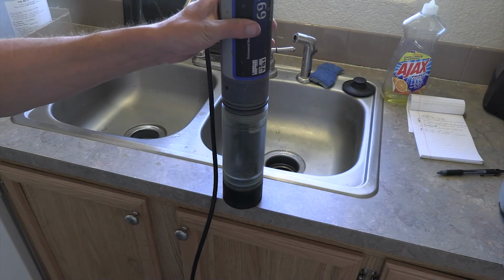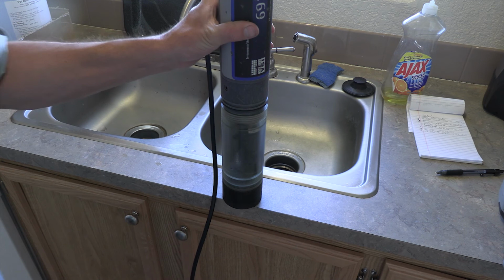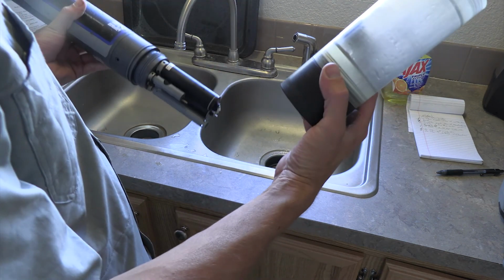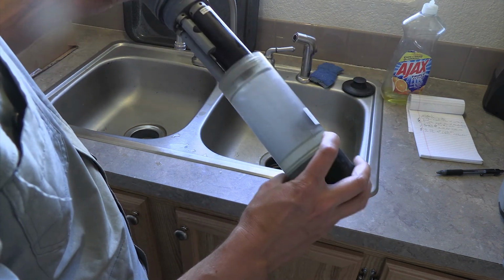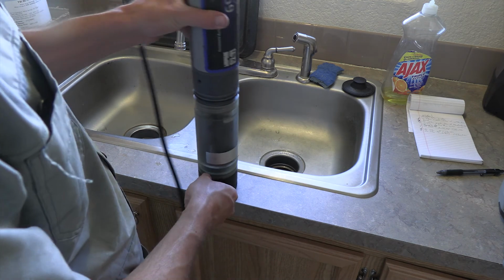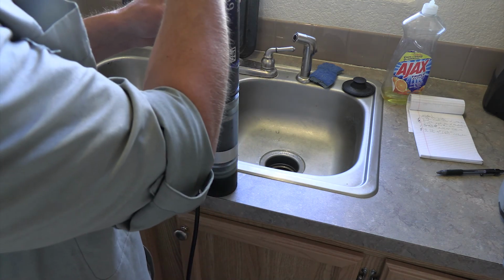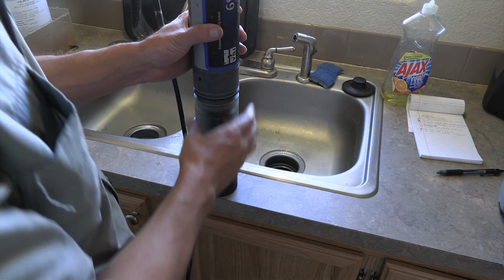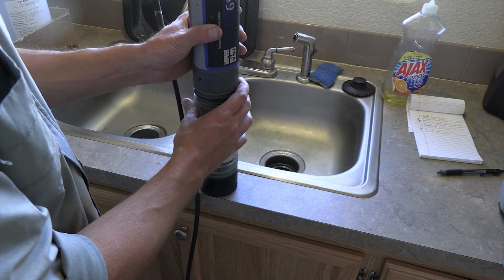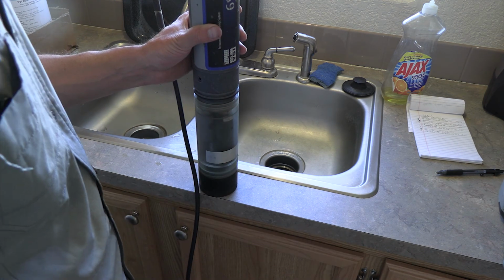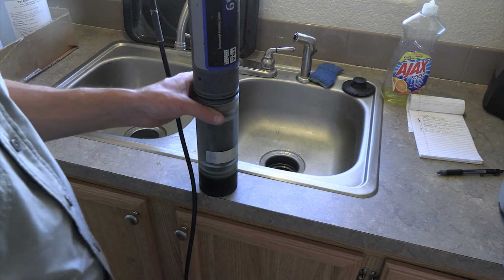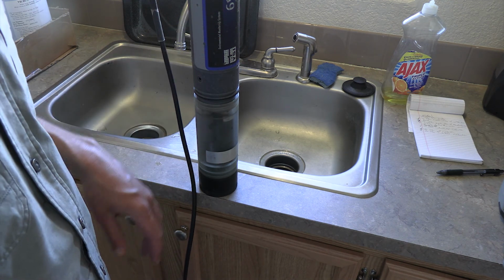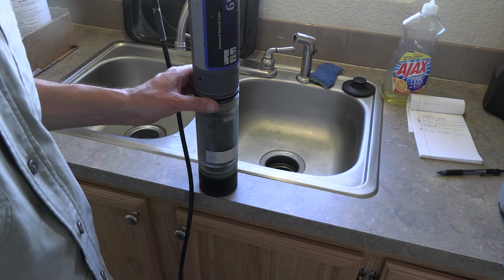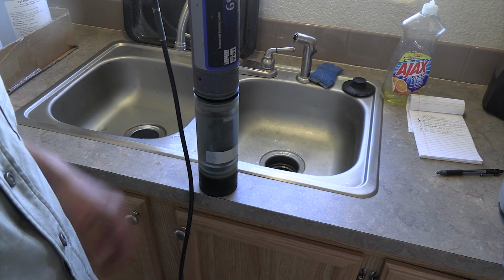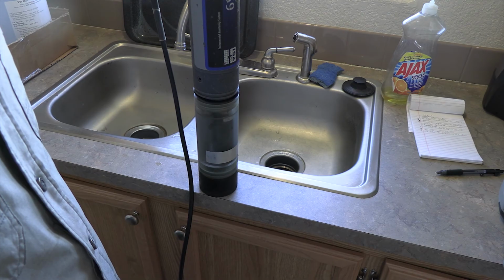So once everything's done, once the measurements are taken, then all you're going to do is just fill up a little bit of water in the calibration cup, screw it back on, and disconnect it if need be, but then take it back out to site and reconnect it. But it should be good to go, as long as the cleaning and the wipers are replaced and all the calibrations are done correctly. And all the notes are done. So thanks. That was calibrating the YSI 6 series Sonde.